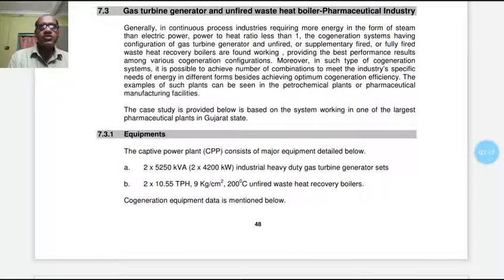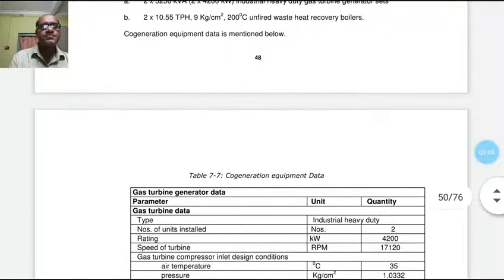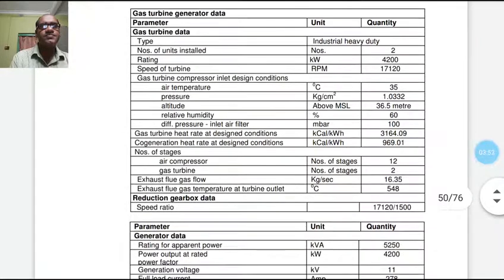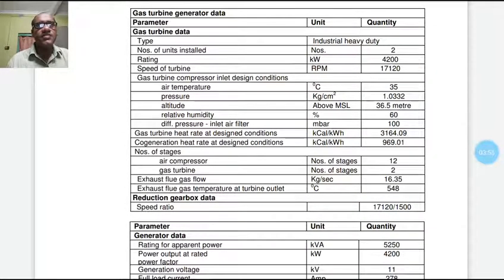Equipment: this captive power plant consists of two major equipment. Details are provided, that is, two numbers of 5250 kVA, which is 2 into 4200 kilowatt industrial heavy duty gas turbine generator sets, and two numbers of 10.55 TPH, 9 bar, 200 degree centigrade unfired waste heat recovery boilers. Cogeneration equipment data for the gas turbine generator: type is industrial heavy duty, rating 4200 kilowatt, speed 17120 rpm.